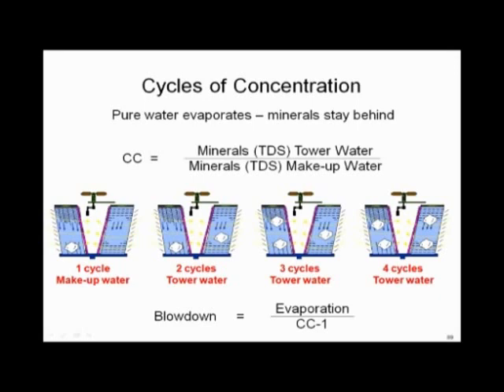When the cooling tower starts up, let's take all the solids and just make them a big rock. We've got one cycle of concentration when we start — 1,000 gallons of water in our tower. When we evaporate that water down, we've got one rock. But when we evaporate that 1,000 gallons down to one rock, we make up another 1,000 gallons of water, and that brings another rock. Now I've got two cycles of concentration: two rocks and 1,000 gallons of water.